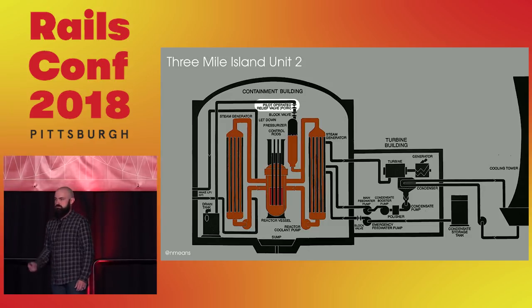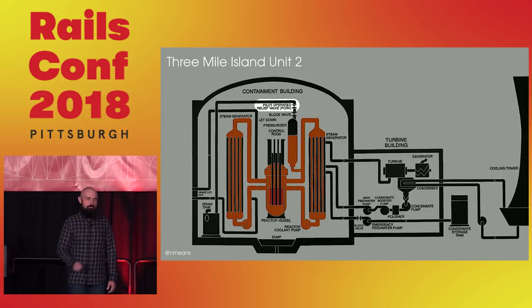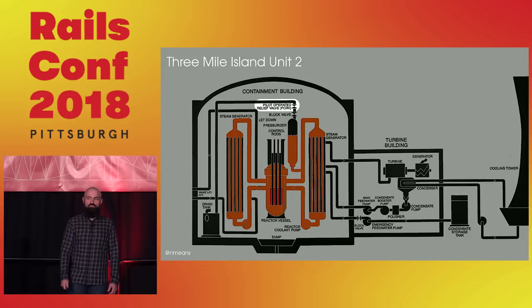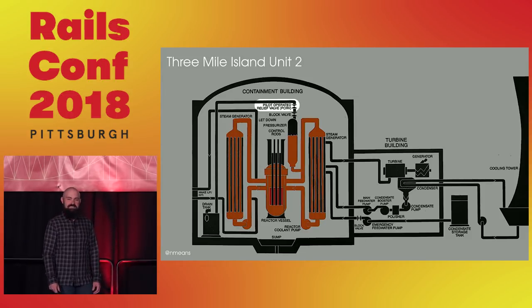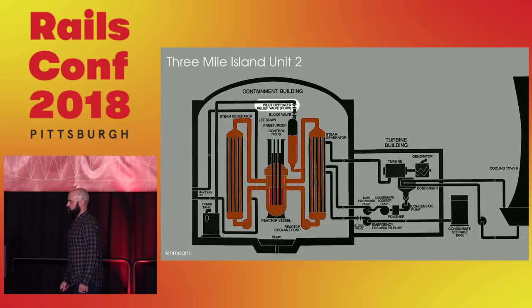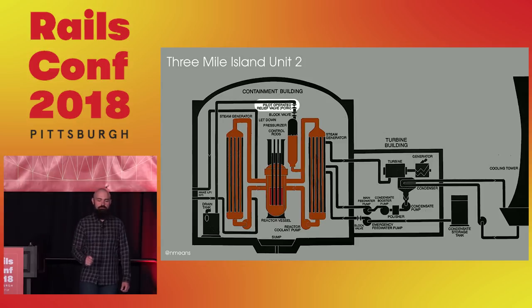They had to constantly adjust the pressure of the primary loop ever so slightly, but it wasn't a big deal. But the consequence of this is that the outlet temperature of the pilot-operated relief valve was regularly over 200 degrees Fahrenheit. And so they had completely desensitized themselves to this rule that they should close the block valve. Bill Zeewee saw the 228 degree reading, and he thought about the fact that the pilot-operated relief valve had just been venting scalding hot water. That seemed like a perfectly reasonable temperature to him, and so he didn't shut the block valve.